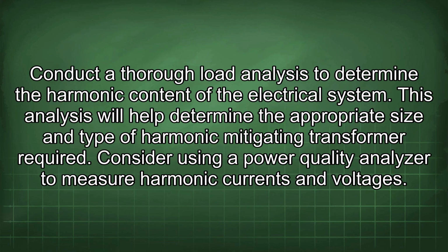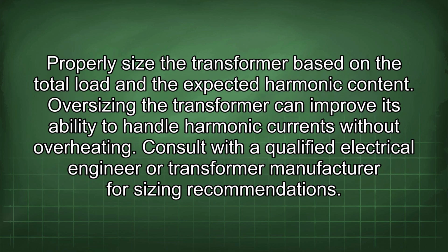Conduct a thorough load analysis to determine the harmonic content of the electrical system. This analysis will help determine the appropriate size and type of harmonic mitigating transformer required. Consider using a power quality analyzer to measure harmonic currents and voltages. Properly size the transformer based on the total load and the expected harmonic content. Oversizing the transformer can improve its ability to handle harmonic currents without overheating. Consult with a qualified electrical engineer or transformer manufacturer for sizing recommendations.